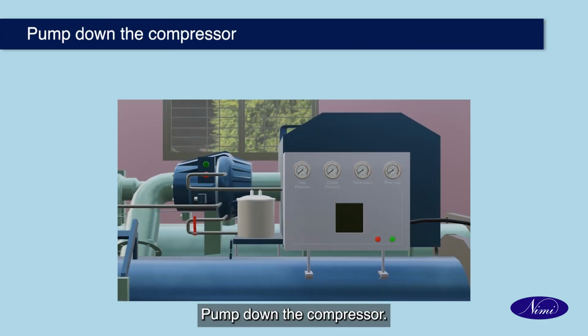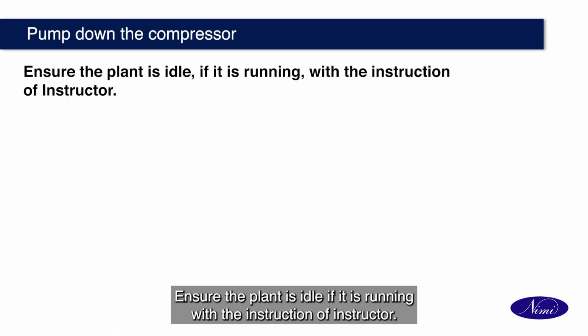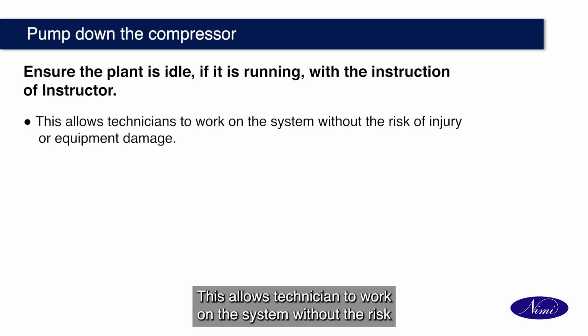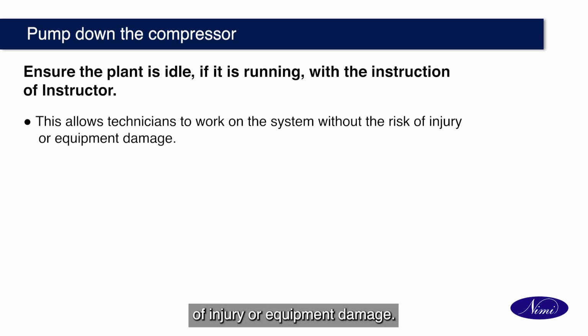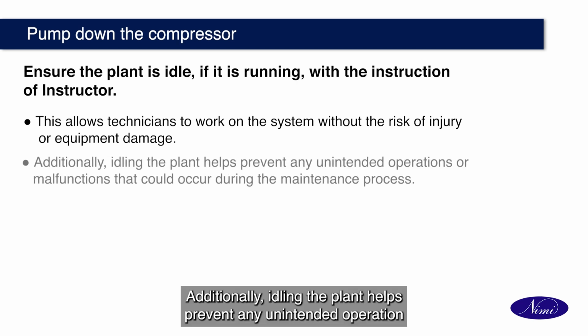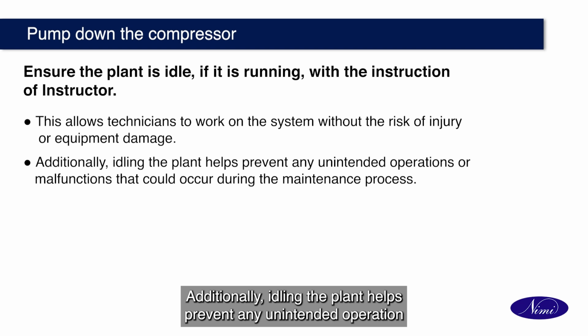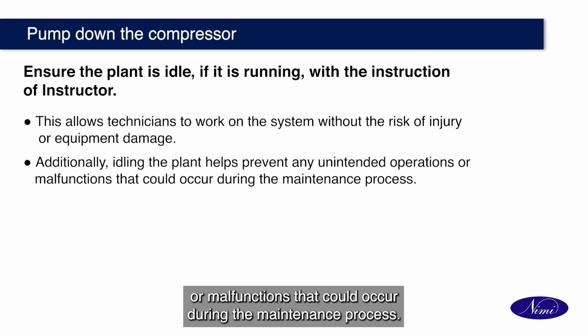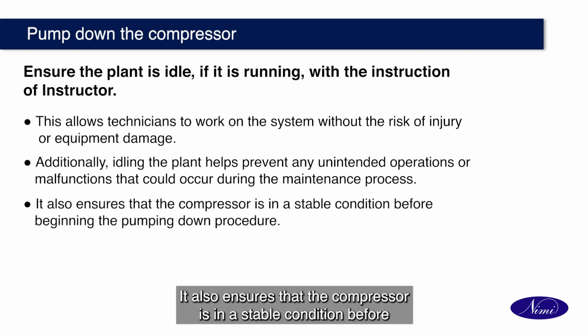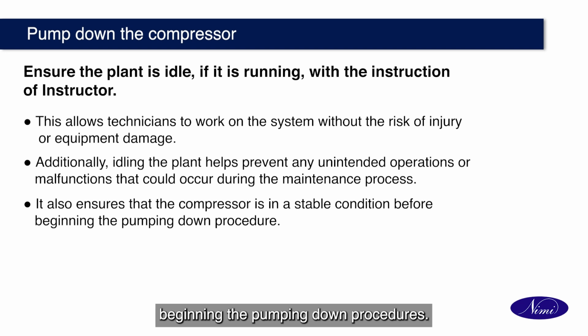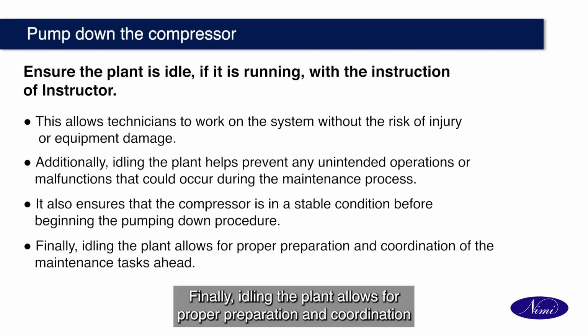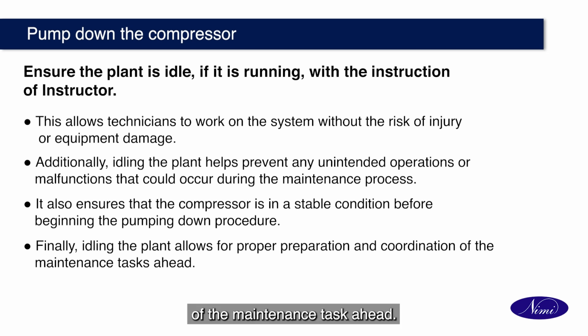Pump down the compressor. Ensure the plant is idle; if it is running, stop it with the instruction of the instructor. This allows the technician to work on the system without the risk of injury or equipment damage. Additionally, idling the plant helps prevent any unintended operation or malfunctions that could occur during the maintenance process. It also ensures that the compressor is in a stable condition before beginning the pumping down procedure. Finally, idling the plant allows for proper preparation and coordination of the maintenance task ahead.